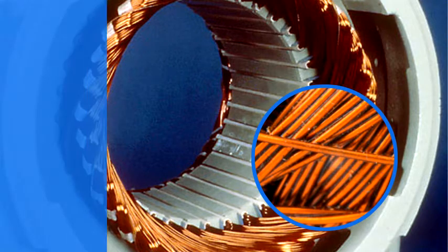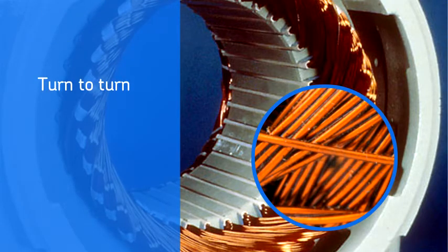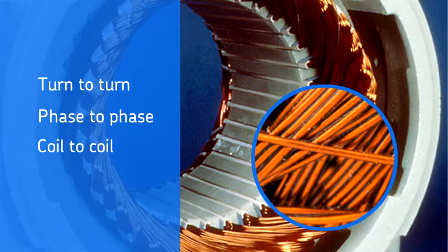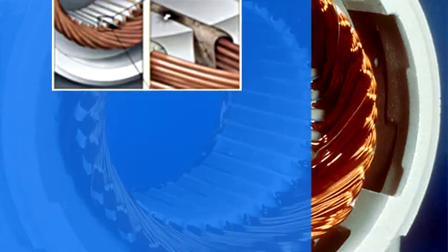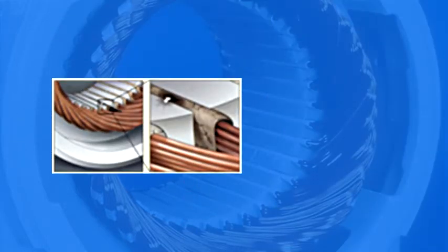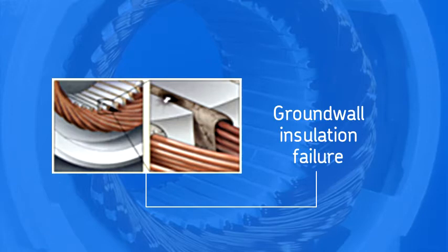This is called a turn-to-turn fault. Other wire-to-wire insulation faults are phase-to-phase and coil-to-coil. When the insulation fails and there is a path to the core, it is called a ground wall insulation failure.